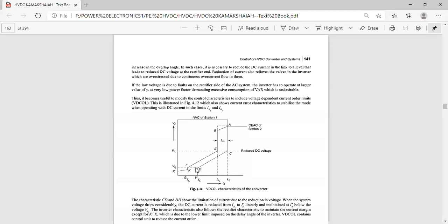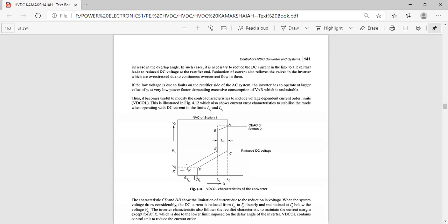These two lines are intersecting at points F and D. Point C is on the rectifier characteristic at current Id1; Id1-dash is the new current of the rectifier. Similarly, Id2-dash is the new inverter current. The difference Id1-dash minus Id2-dash is the new current margin Idm-dash. This is the voltage dependent current order limit — based on the reduced voltage, we define new currents for the rectifier and inverter.